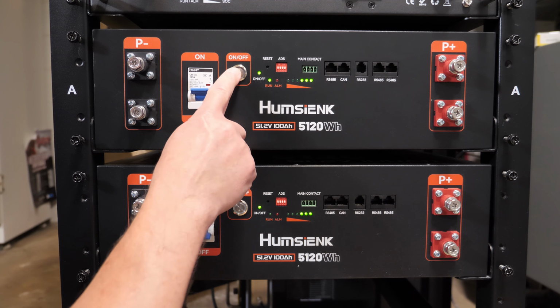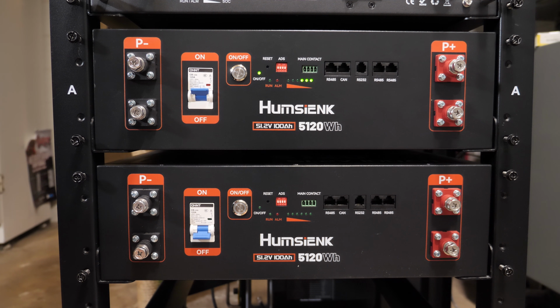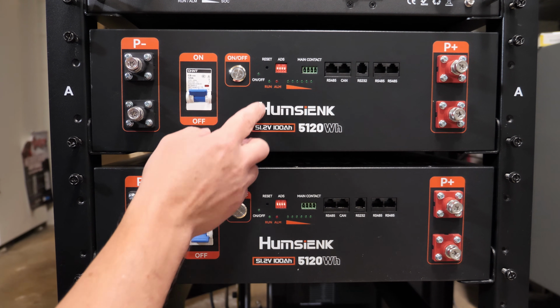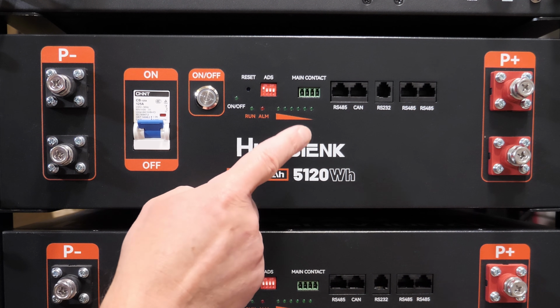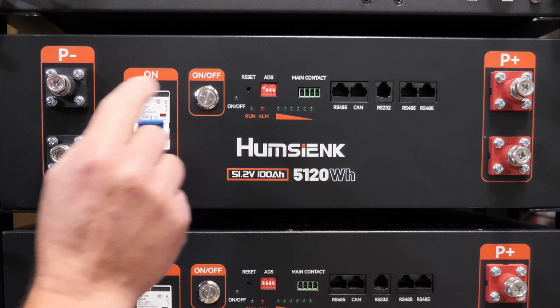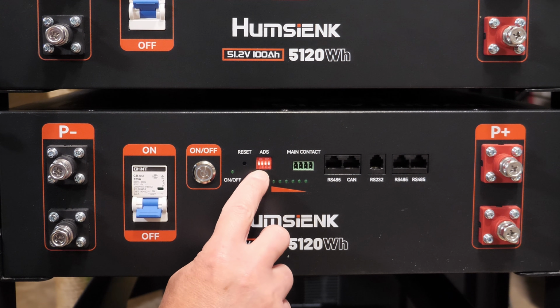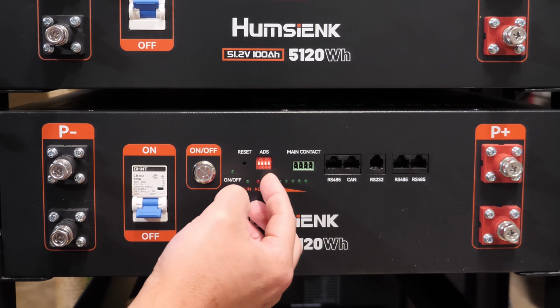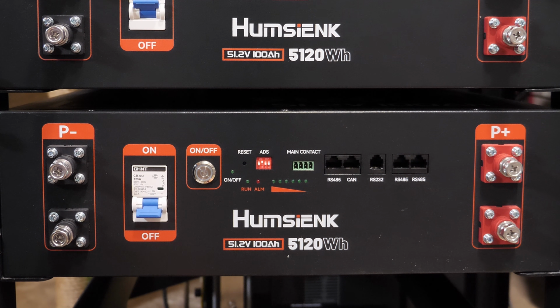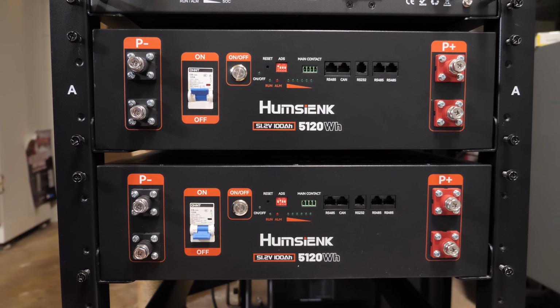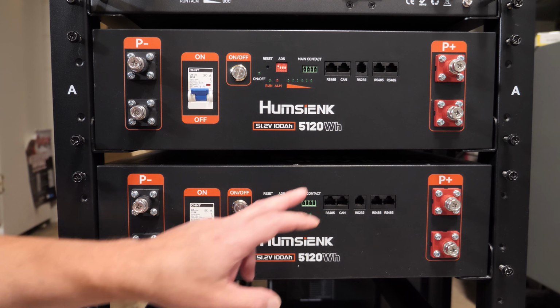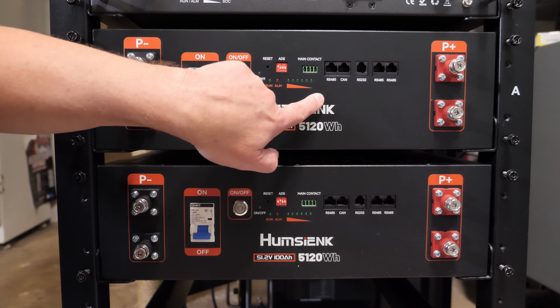All right, I'll start by turning both batteries off. Step 1 is the address dip switches, basically assigning each battery an address. So in the manual, it says to put battery 1, or the master battery, first switch up, and then down here for battery 2, it says the second dip switch will be in the up position. Boom, there we go. Step 2, communication between the battery and inverter uses RS-485 communication. The inverter must be configured with the correct BMS communication protocol, while the battery BMS will automatically match the protocol once properly connected. Okay, we'll connect up to RS-485 on the master battery right here in just a second.